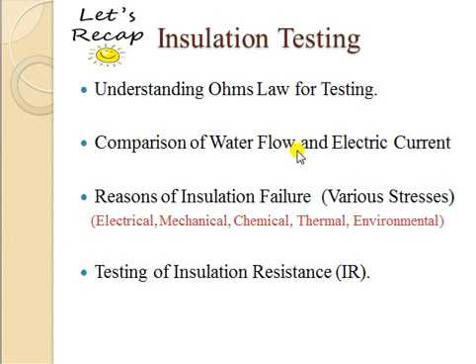How to test insulation resistance — the equipment principle for insulation resistance testing, which we call an insulation tester, simply applies voltage across your insulation, measures the amount of current flowing through that insulation, and by applying Ohm's law, V/I, it calculates your resistance.